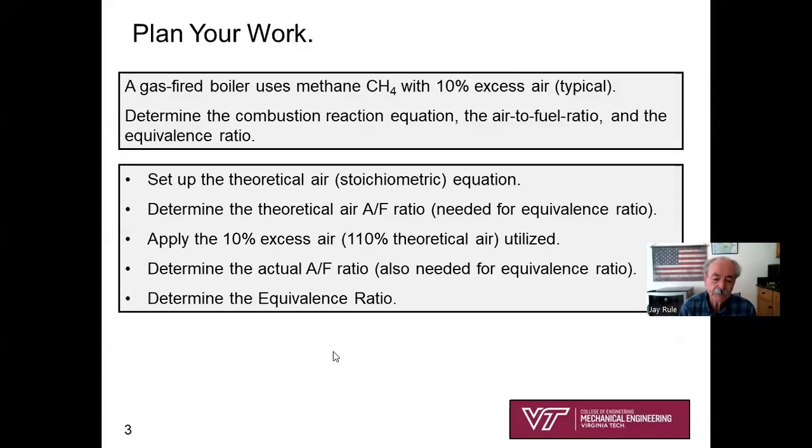So the next thing you're going to do is apply the 10% excess air factor. Remember, there was that factor 1.1 for 10% excess air. Or in other words, I could have worded it 110% theoretical air. It's very common. Different engineers use different jargon. Some engineers will say 10% excess air, some engineers will say 110% theoretical air. It means exactly the same.